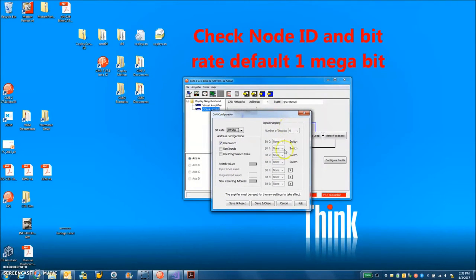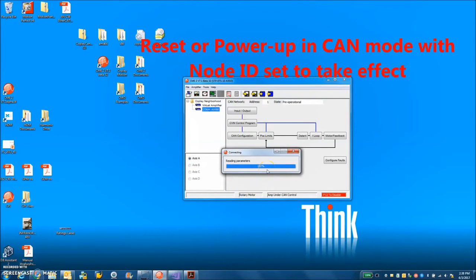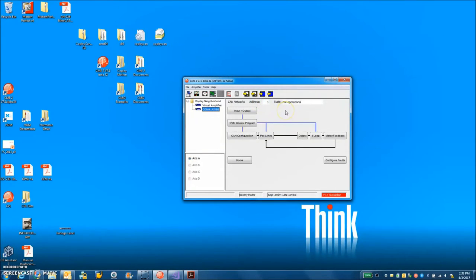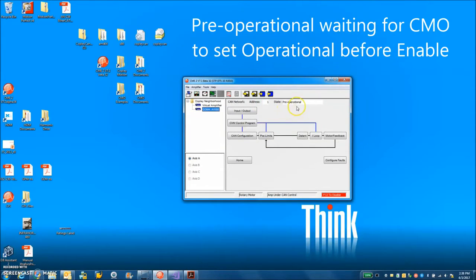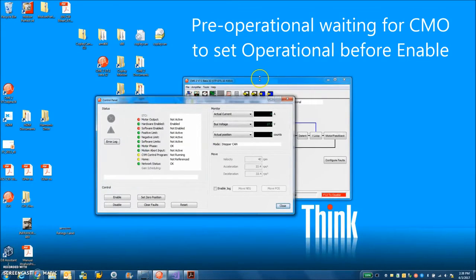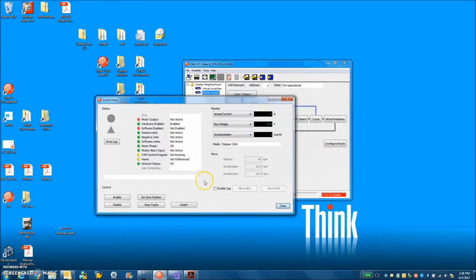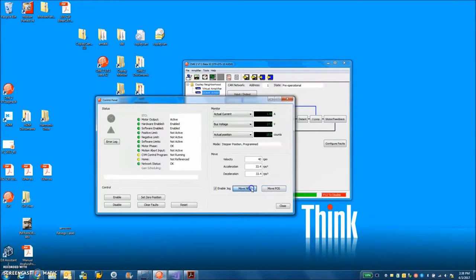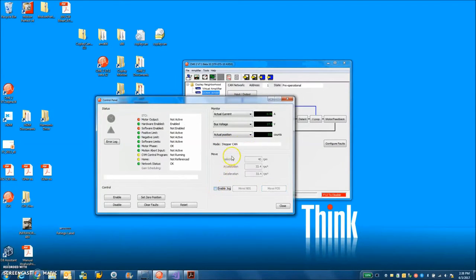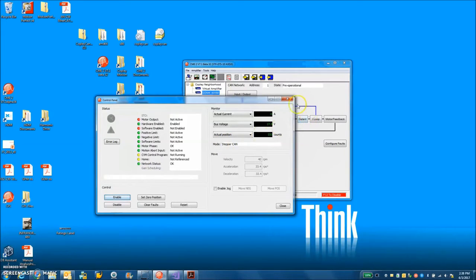The current node ID is 1 but if it was 0 like you just changed the switch then you'd have to reset the drive. So the drive comes up, looks at the switch, assigns address 1. The drive comes up in a pre-operational state. You can see on the control panel it's mode CAN stepper. If I start jogging things to test things out that's really cool and lots of fun but don't save the stepper program position flash and don't leave it in a disabled mode. Make sure it's in a CAN mode. So enabled in CAN mode.